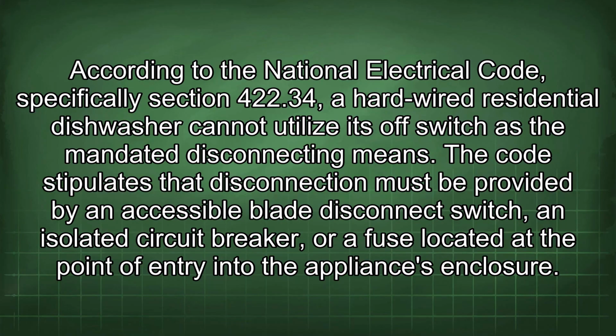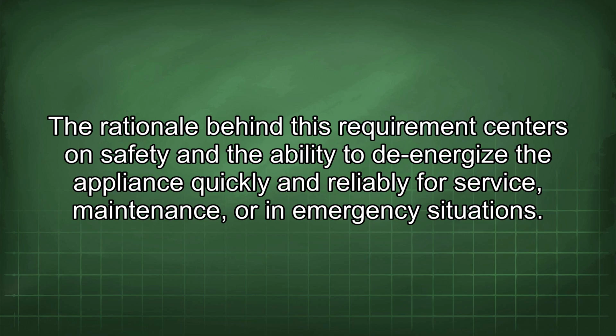According to the National Electrical Code, specifically Section 422.34, a hardwired residential dishwasher cannot utilize its off switch as the mandated disconnecting means. The code stipulates that disconnection must be provided by an accessible blade disconnect switch, an isolated circuit breaker, or a fuse located at the point of entry into the appliance's enclosure. The rationale behind this requirement centers on safety and the ability to de-energize the appliance quickly and reliably for service, maintenance, or in emergency situations.